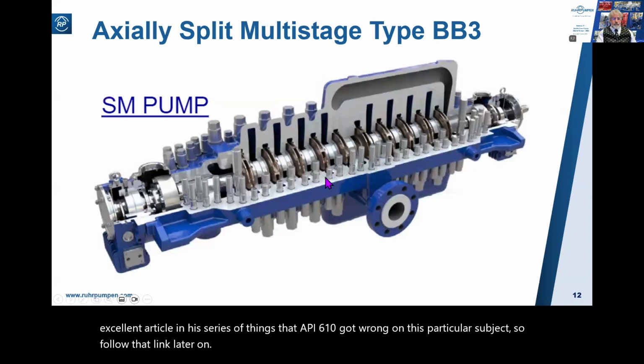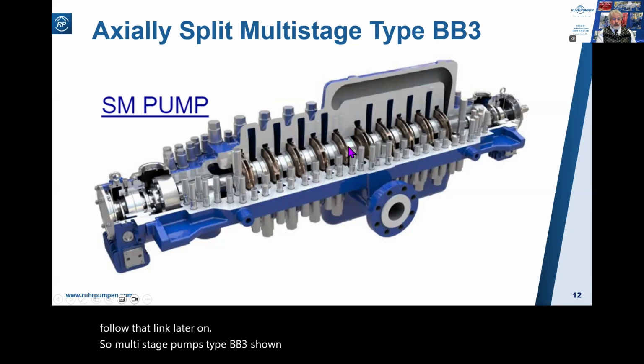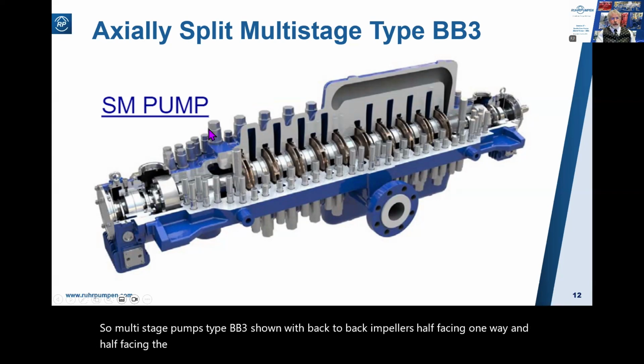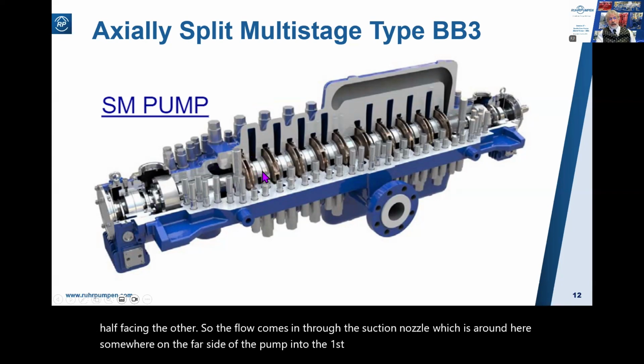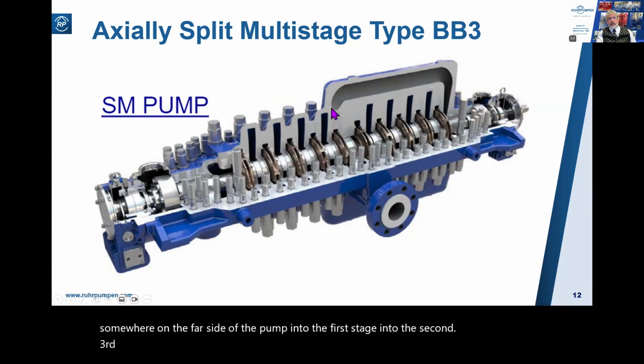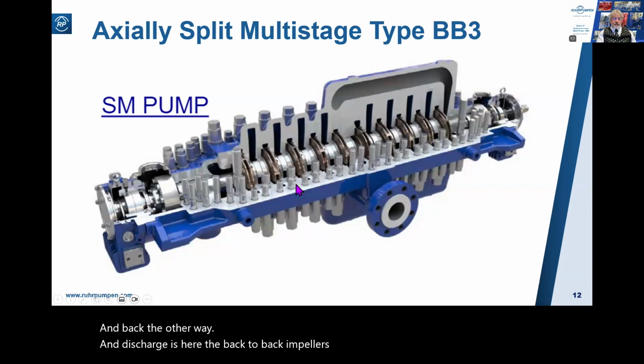So, multi-stage pumps type BB3 shown with back-to-back impellers, half facing one way and half facing the other. So the flow comes in through the suction nozzle, which is around here somewhere on the far side of the pump, into the first stage, into the second, third, fourth, fifth. Then it goes into this crossover and back the other way and discharges here. The back-to-back impellers balance the thrust, so you just have lightly loaded thrust bearings.